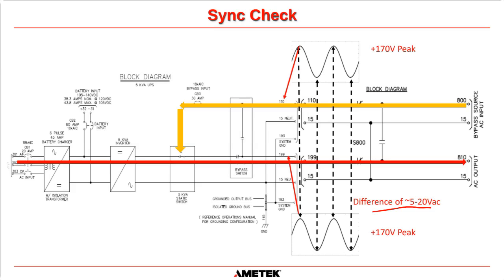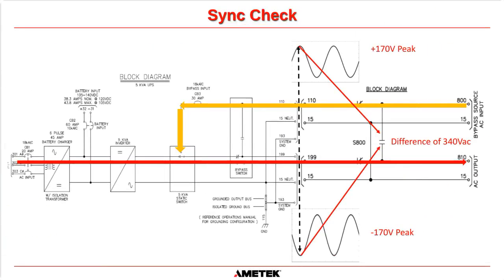Actually, on this slide here, I said you're going to see approximately a difference of 5 to 20 volts on a healthy system that is in sync. Okay. Now, for a system that is out of sync, you can see here that we are at the top of our sine wave here, but we're in the trough. We are at the bottom of the sine wave here because at that moment they are completely out of phase. Then across wire 110 and 199, or you can even do it in the bypass switch if you want, there is going to be a difference of 340 volts at the peaks. Okay.